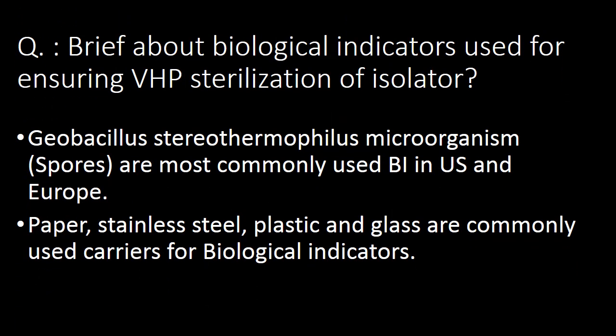Brief about biological indicators used for ensuring VHP sterilization of isolators: Geobacillus stearothermophilus microorganism spores are commonly used as biological indicators in the US and Europe for ensuring VHP sterilization of isolators. Paper, stainless steel, plastic, and glass are commonly used carriers for these biological indicators.